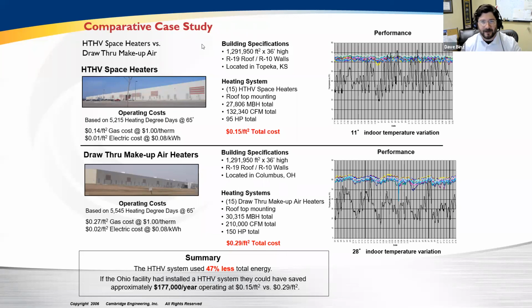Both had 100% outside air. Both had 100% combustion efficiency devices. But that simple fact of having high temperized, high velocity, and blow-through equated to massive energy changes. The building that utilized the Cambridge system saved about $177,000 a year in electrical and gas costs. So whenever we hear that draw-through makeup air is just like a blow-through HTHV, there are massive energy cost savings to our end users. When this customer found this out, a few years later they took off those fairly new draw-through makeup air units, put in a blow-through, and have been saving tremendous amounts on gas and electrical bills over the years.